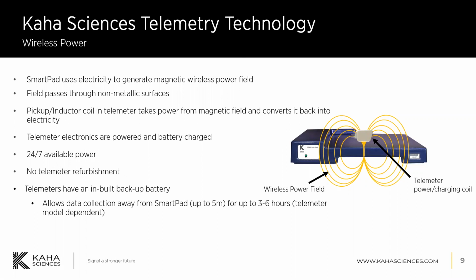As well as the benefits of the wireless power field, the telemeters do have this built-in battery. And what this allows is data collection away from the smart pad. So up to 5 meters away for between 3 to 6 hours, depending on the model of the telemeter. And what this means is that you can use our system for behavioral studies as well as continuous home cage monitoring. So if you were running your rat in a maze, for instance, or if from a cardiovascular point of view, you're doing exercise studies or something like that, you can do this with our system. And then once you've finished that part of your experiment, you can put the rat back in the home cage and the battery will be recharged by the wireless power of the smart pad.